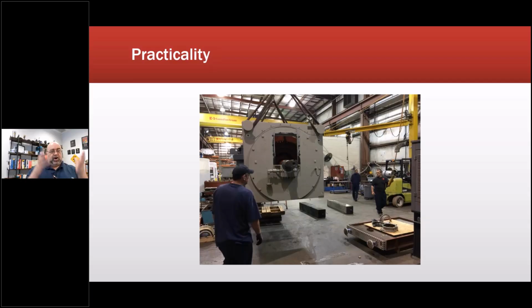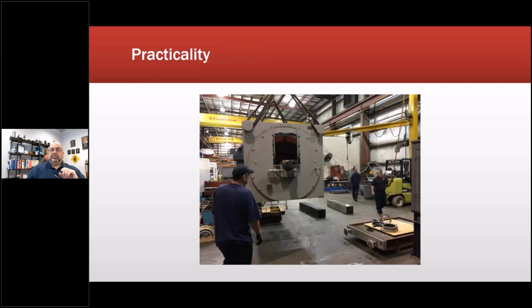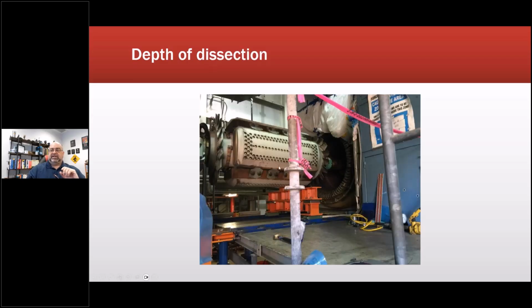When we took off the hood, that's when we identified this additional thing that was a latent issue that was not part of the original problem. So when we start getting into tearing them down, this is the dissection. This was my 24 megawatt cogen unit at National Institutes of Health, in which we were doing an investigation there too. You know, these can be quite exciting.